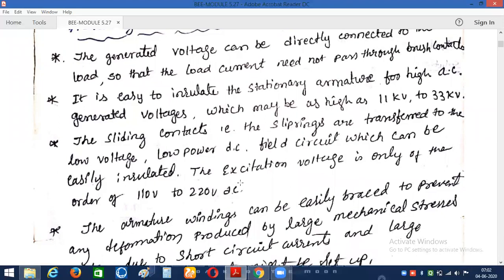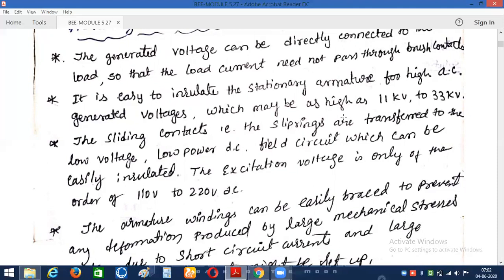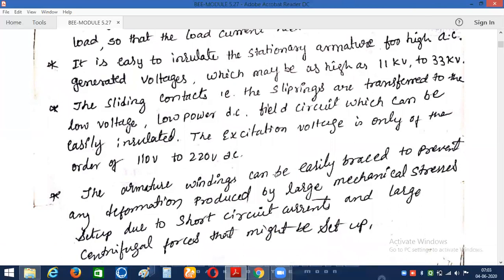It is also easy to insulate the stationary armature. When the armature is rotating, it is a very tough task for engineers to provide insulation. Rather than dealing with a rotating armature, making it stationary makes insulation much easier. Here we are using voltages in the order of 11 kV, 32 kV, or 33 kV, so for such high voltages it is better to make the armature conductors stationary.